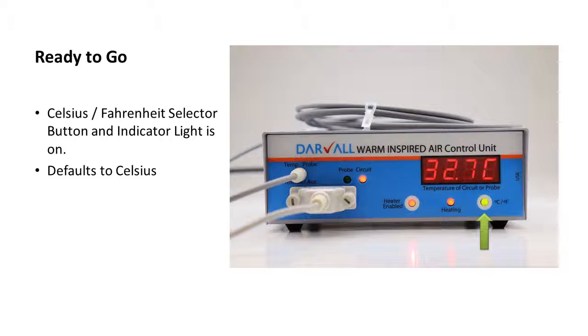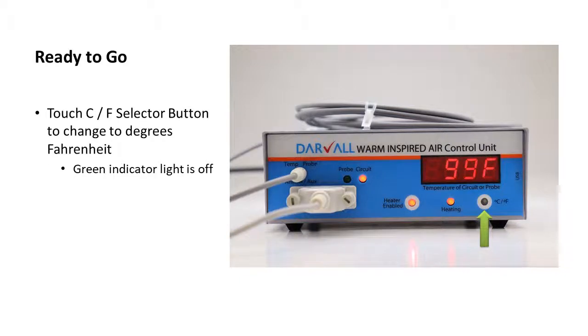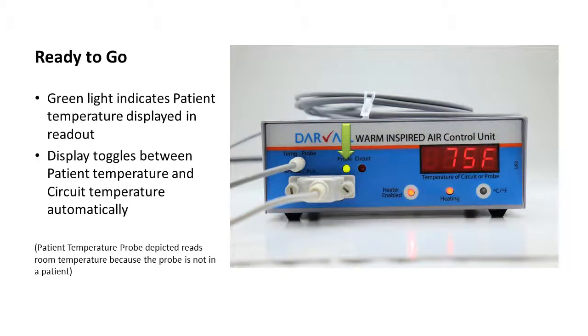The green Celsius Fahrenheit indicator light is on. The control unit defaults into Celsius reading. Touch the CF selector button to change the degrees to Fahrenheit. The green light turns off when the unit displays temperature in Fahrenheit. The display in the LED readout panel toggles between probe temperature and circuit temperature automatically. When the green light is on, it indicates the readout displayed in the panel is the patient's temperature. The patient's temperature depicted in this picture reads room temperature because the temperature probe is not in a patient.